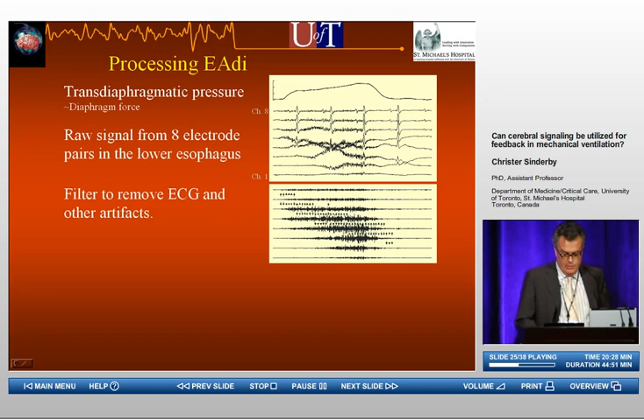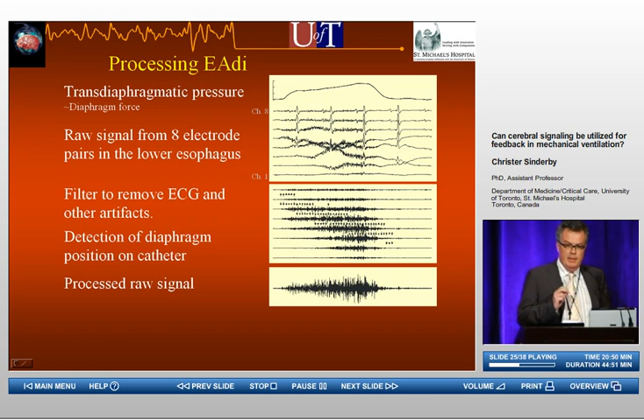In order to use this signal, we have to take away artifacts. And I'm not going to go through how we do it, but we do it. We also have to detect where the diaphragm is because it moves. And the electrode moves, the esophagus moves, everything moves. So we have to know where on this catheter we are at all times. Finally, we have a processed signal. And now you can start to see that there is actually some increase throughout that inspiration. So going from the start of an inspiration to maximal inspiratory capacity, you see there is an increase in that activity.